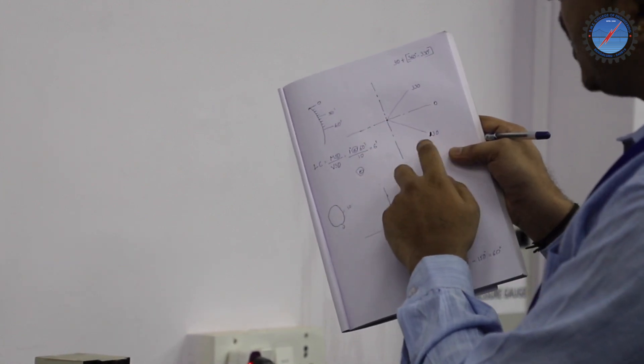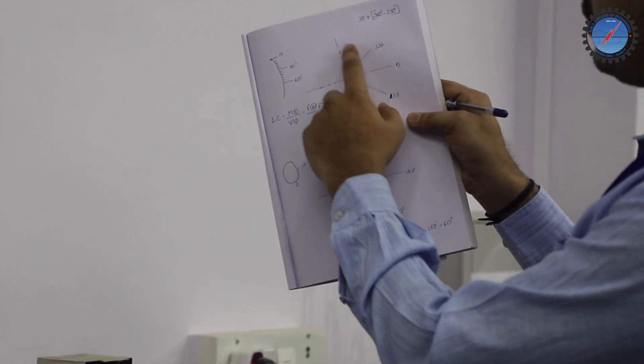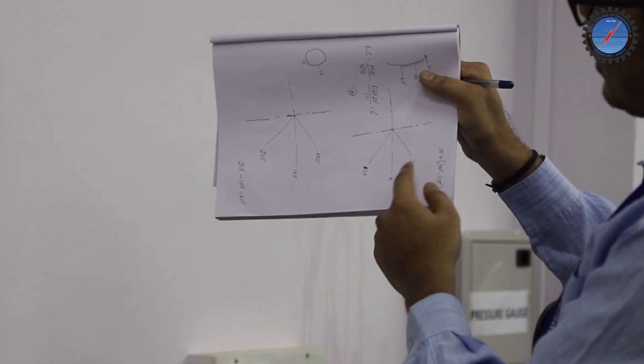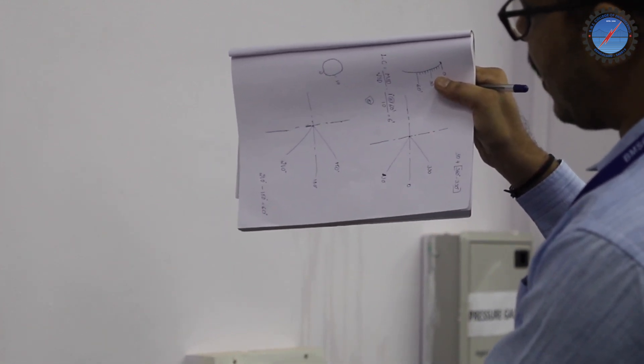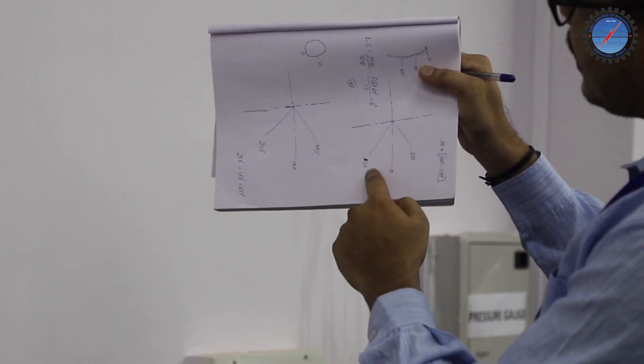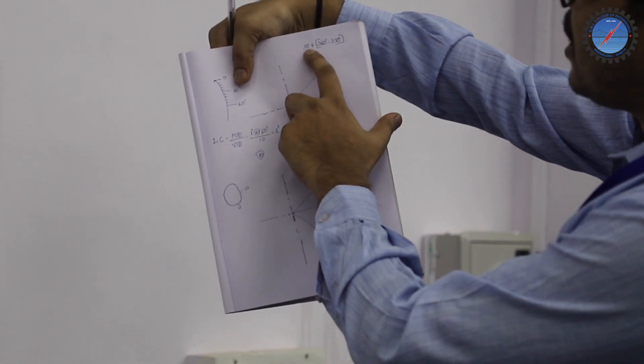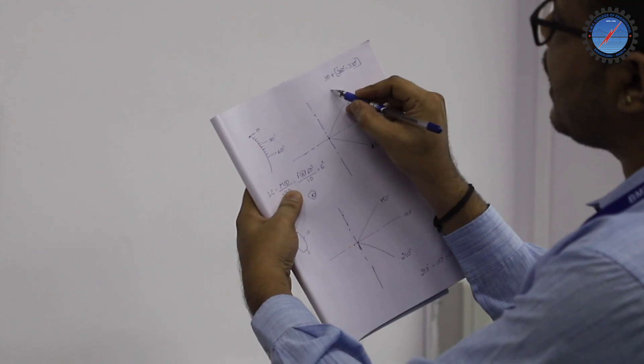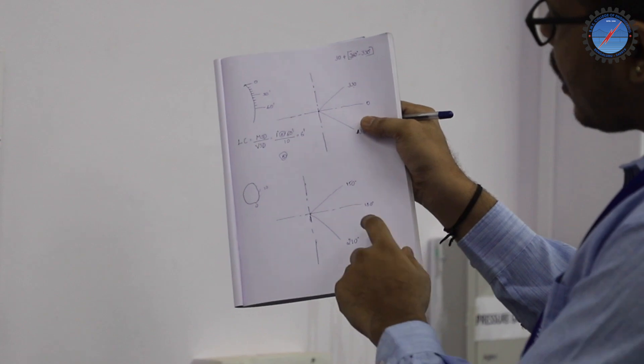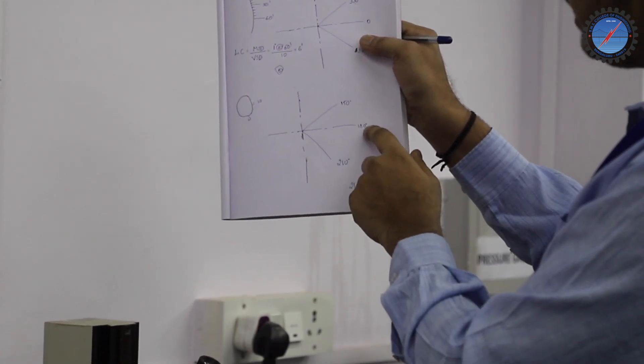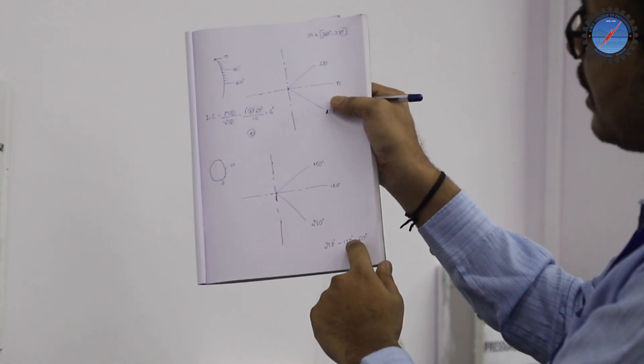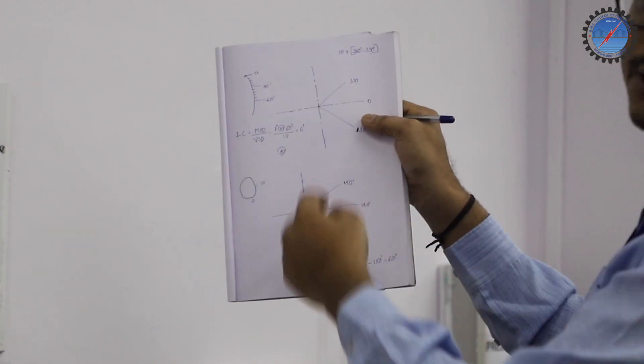To measure the angle, look through the eyepiece crosshair and align it with one side of the V-thread. One reading will show around 330 degrees and the other around 30 degrees. Subtract 330 from 360 to get the reading, or alternatively, rotate the protractor to start at 180 degrees — one reading will be about 150 degrees and the other about 210 degrees. Subtracting 210 minus 150 directly gives 60 degrees. Either of these two methods can be used.